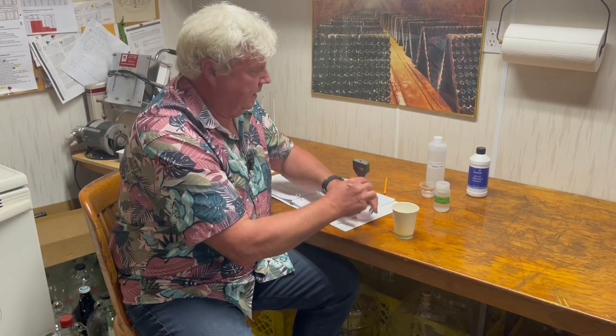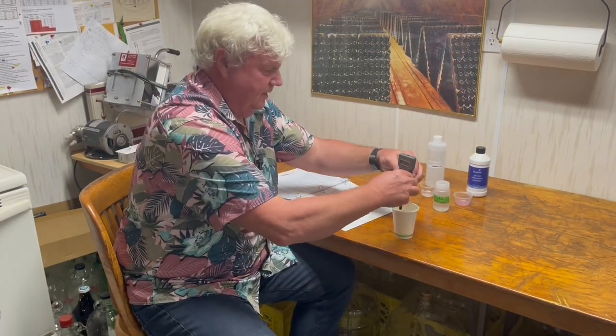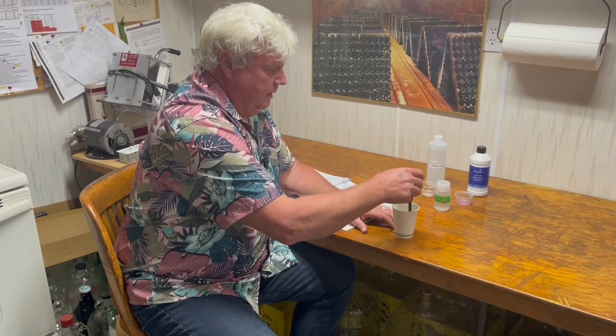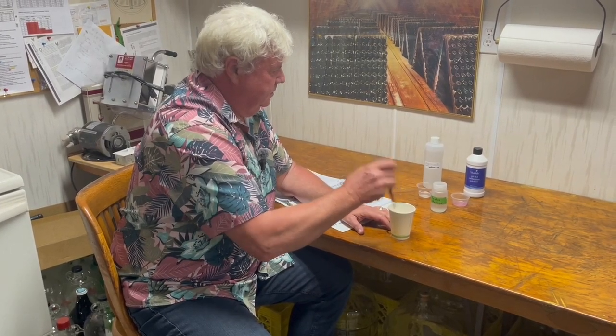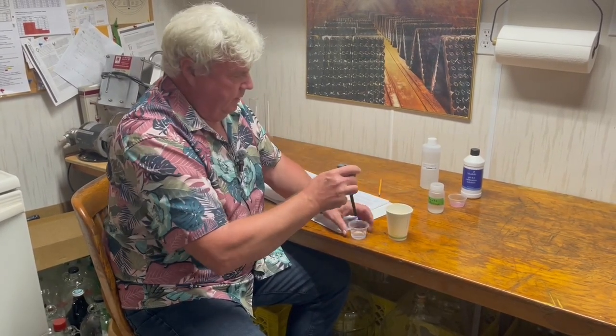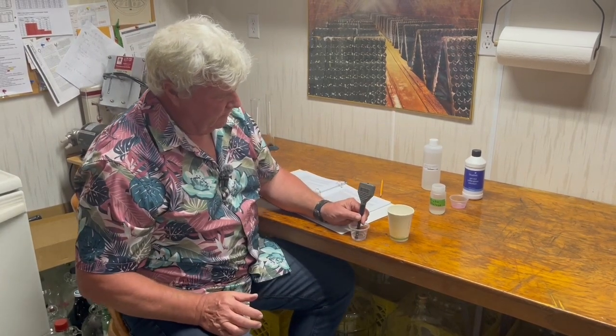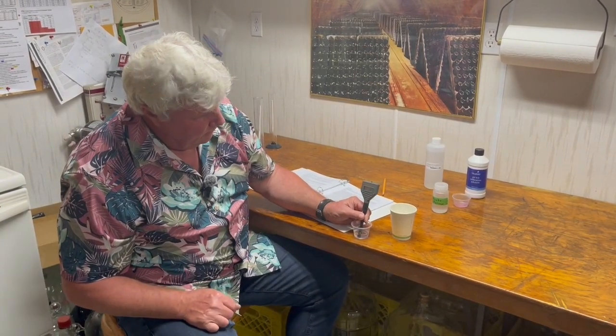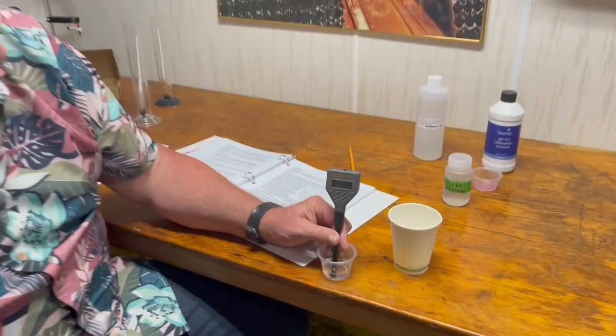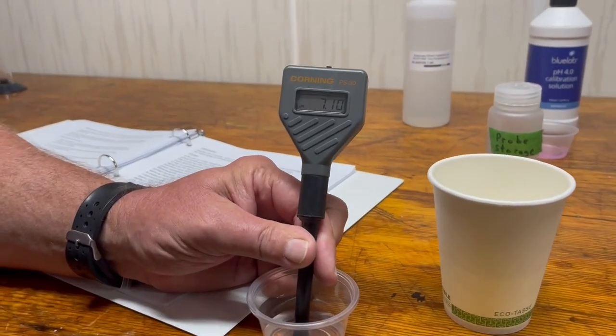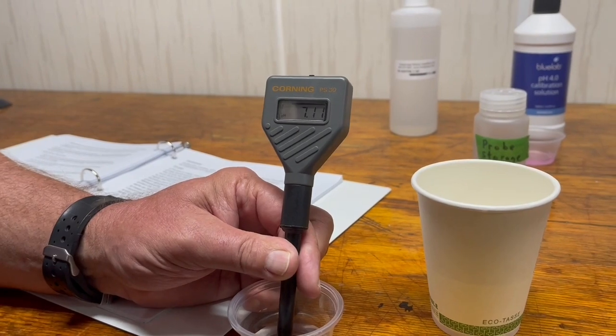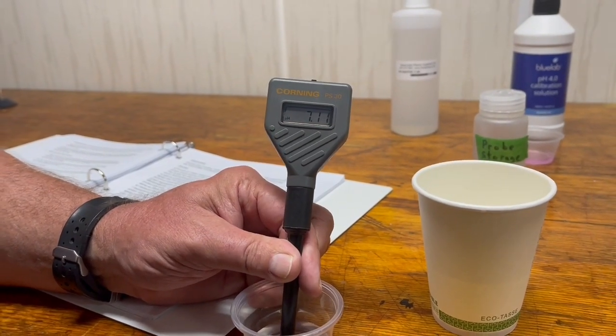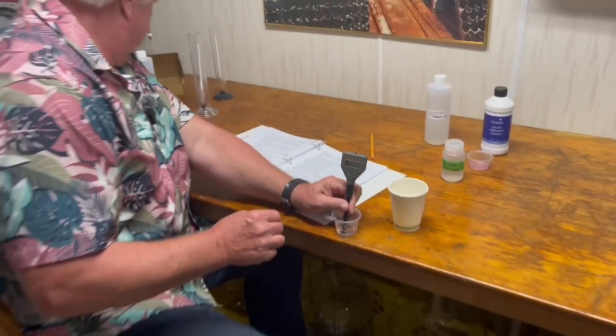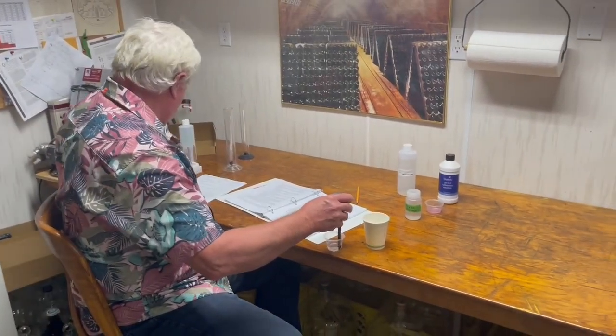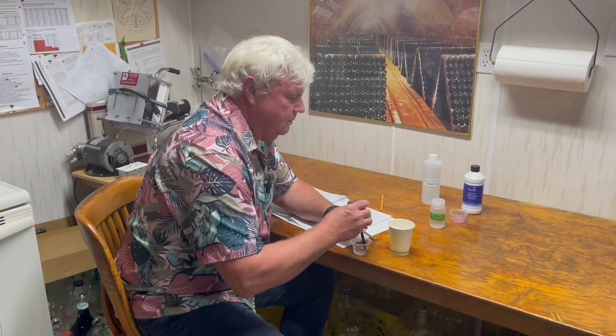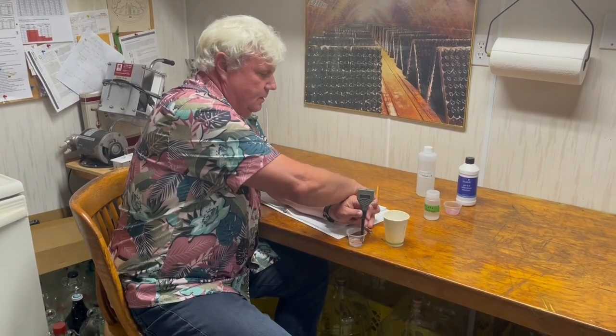Okay, so once you have that one done, and I just calibrated this one, so I know it shouldn't need it, rinse it out in the distilled water again, shake it off, and put it in the buffer solution for 7, and this should read 7. If you zoom in on that, this one's reading 7.11. So it's a little bit out. So I'll use a little screwdriver there, making sure I've got the right one.